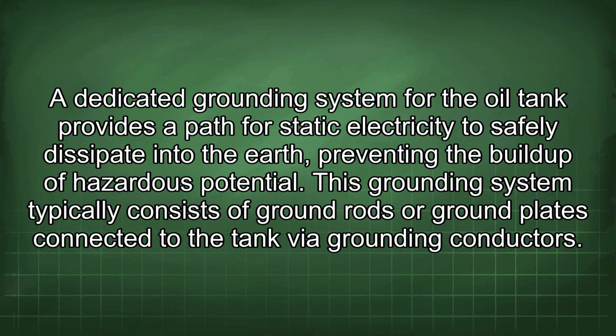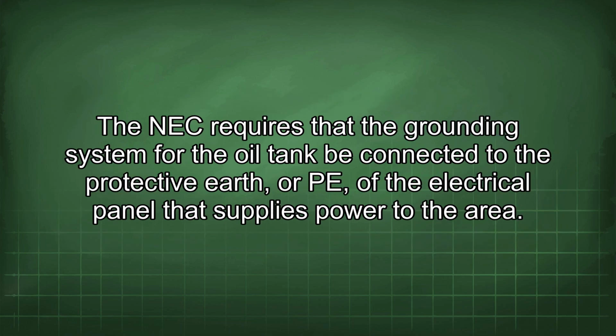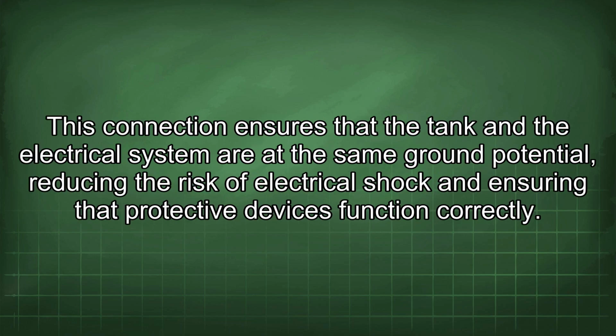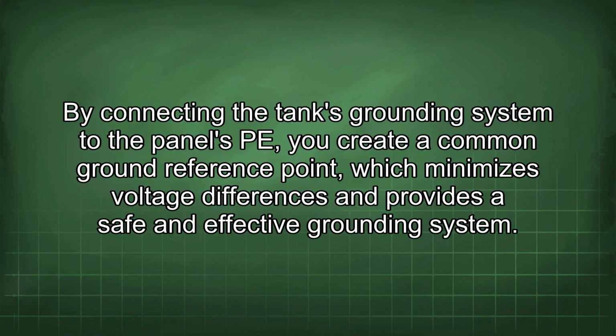This grounding system typically consists of ground rods or ground plates connected to the tank via grounding conductors. The NEC requires that the grounding system for the oil tank be connected to the protective earth, or PE, of the electrical panel that supplies power to the area. This connection ensures that the tank and the electrical system are at the same ground potential, reducing the risk of electrical shock and ensuring that protective devices function correctly. By connecting the tank's grounding system to the panel's PE, you create a common ground reference point, which minimizes voltage differences and provides a safe and effective grounding system.